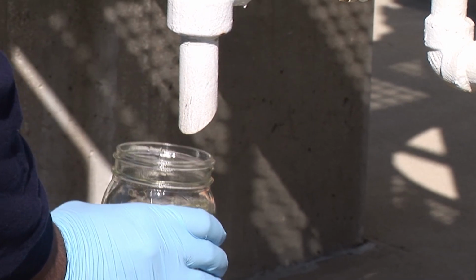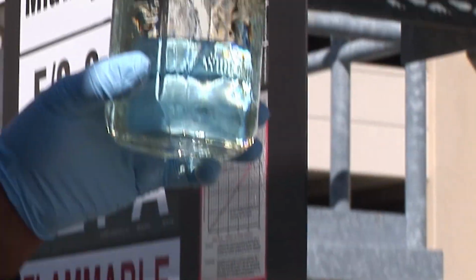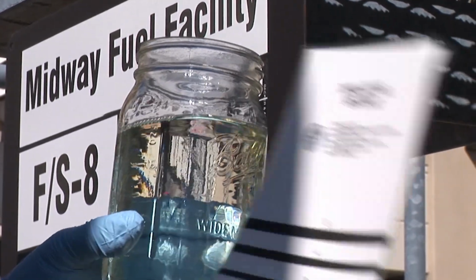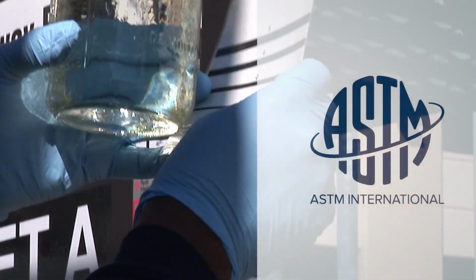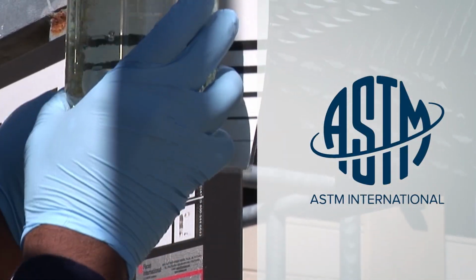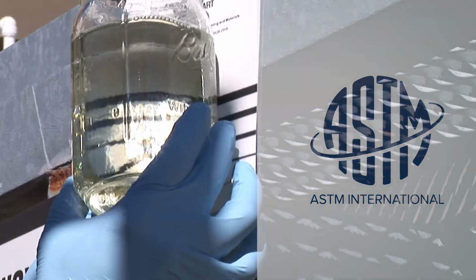In the clear and bright test, fuel samples are taken in a glass jar or beaker and checked for brightness and clarity. Detailed descriptions and recommended procedures for each of these tests can be found in the ASTM manual.